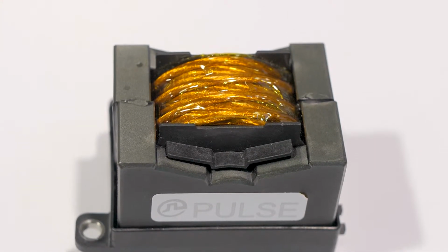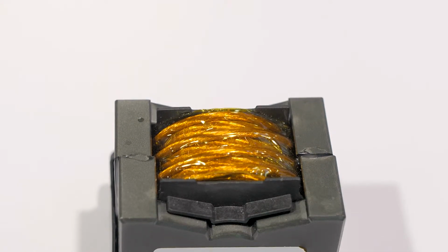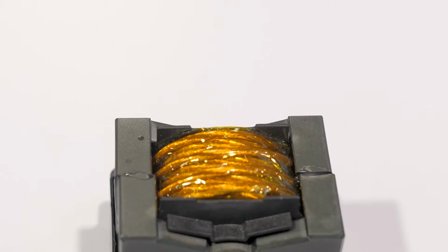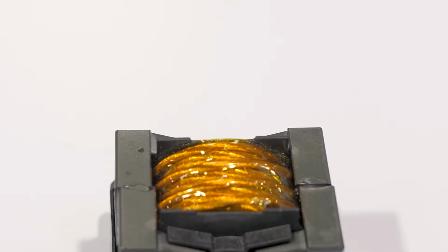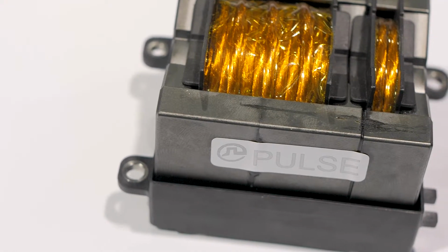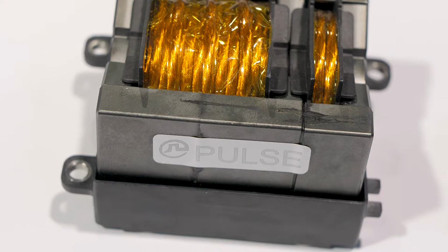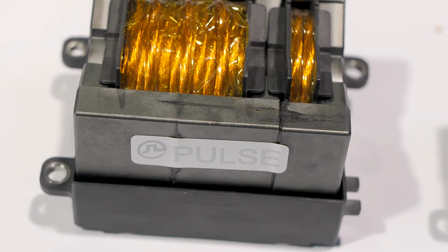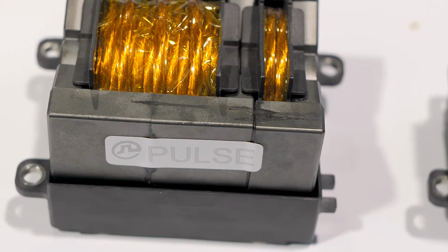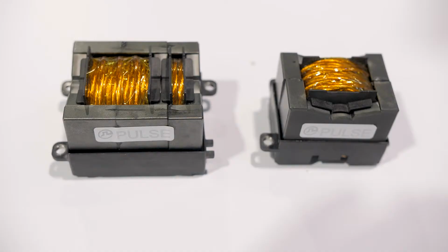What about magnetic materials? Are you seeing any problems that arise when you change materials? Absolutely. There's a lot of different materials out there. A lot of the materials are advertised that they can do a certain function, but then when you go to use them in that way, you find out little gotchas, little problems that maybe are different. As you take a core shape and change it, make it smaller, change the construction, it also adds to the losses. And there's no way to anticipate that. So you have to do a lot of testing.